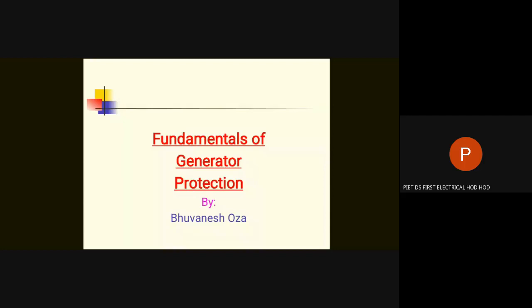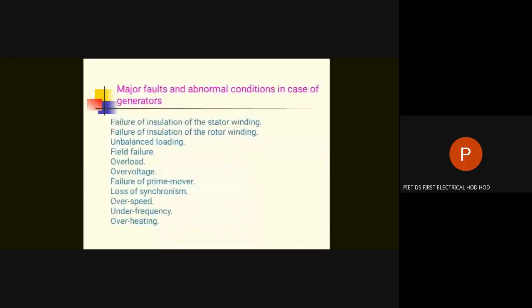The protection of a generator is in a way a little complicated, because if there is a fault in the transmission line, just tripping the breaker to isolate the fault is sufficient. That means the faulty part will be isolated from the remnant of the healthy system. In a generator it is not like that. The generator is connected to the bus via a breaker. If you trip the breaker, the fault will not be isolated, because if there is an internal fault, the generator will keep on feeding its own fault.